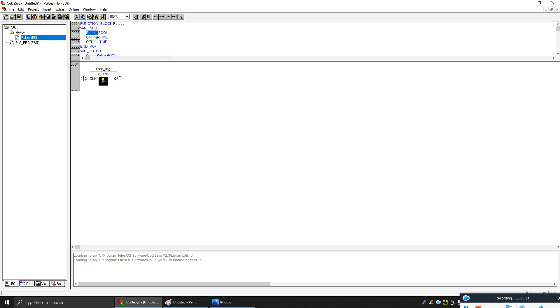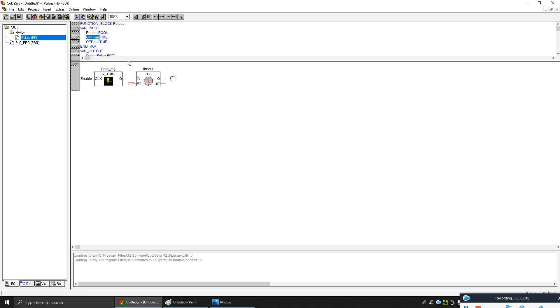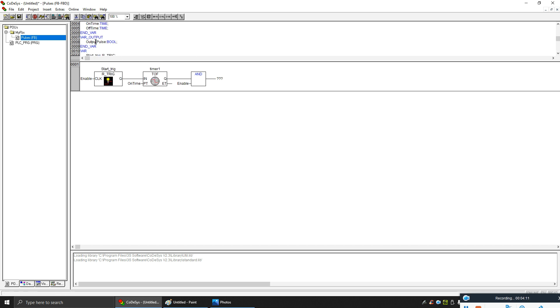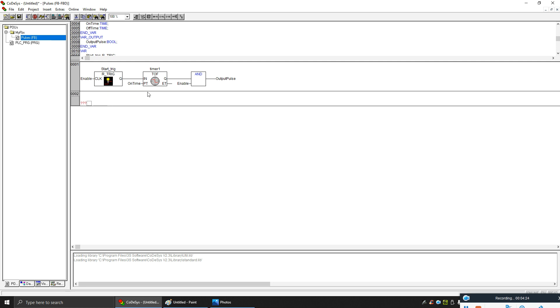I'll be using my enable input to start my timers. This will be my on-pulse time function block, and my output will come from here. Now my on pulse is ready. Now I need to create an off pulse. My off pulse should start once my on pulse finishes, so I'll make an F-trigger off this one.